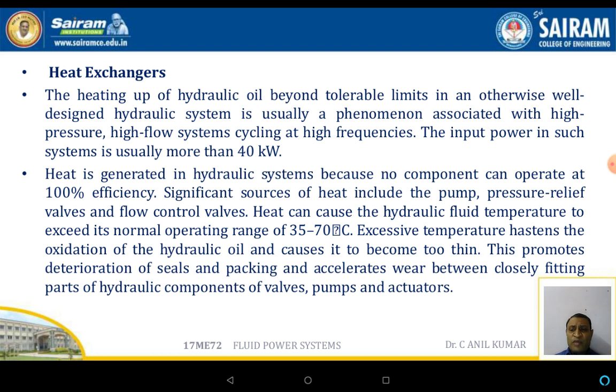Heat exchangers are used when hydraulic oil exceeds a tolerable limit. In a well-designed hydraulic system, heat generation is a usual phenomenon associated with high pressure, high flow systems cycling at high frequencies. Heat is generated because components cannot operate at 100% efficiency. Significant sources of heat include pumps, pressure relief valves, and flow control valves. Heat causes hydraulic fluid temperature to exceed its normal operating range of approximately 30 to 70 degrees centigrade.